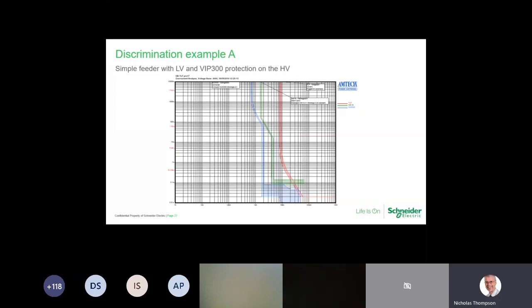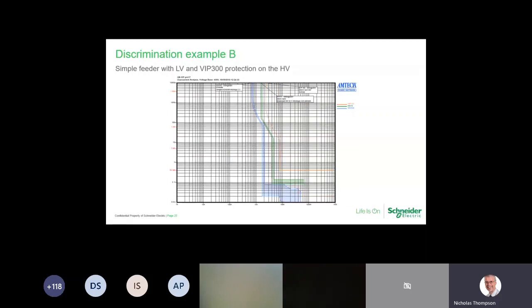Just by changing from time limit fuse to VIP, we can manipulate the protection curves a lot more easily. So we've gone for an inverse curve and a definite time curve, and we've got good clear coordination between all three devices. This is where the juggling starts, and again it's down to a protection study, which will determine the best way forward.